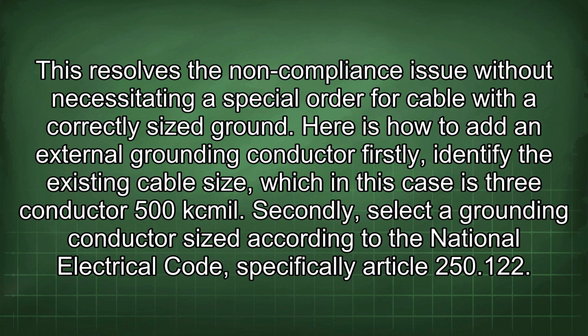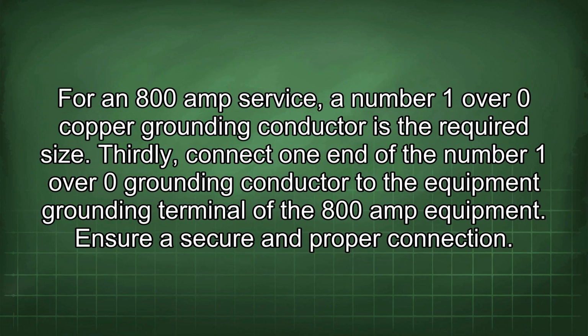Firstly, identify the existing cable size, which in this case is 3-conductor 500 kcmil. Secondly, select a grounding conductor sized according to the National Electrical Code, specifically Article 250.122. For an 800 amp service, a number 1/0 copper grounding conductor is the required size. Thirdly, connect one end of the number 1/0 grounding conductor to the equipment grounding terminal of the 800 amp equipment. Ensure a secure and proper connection.